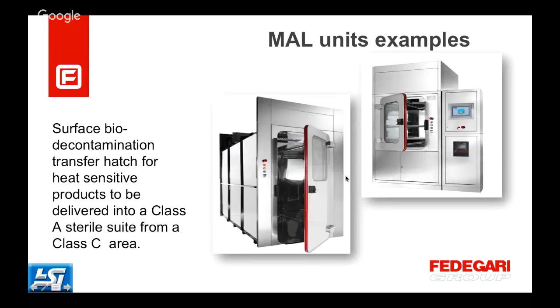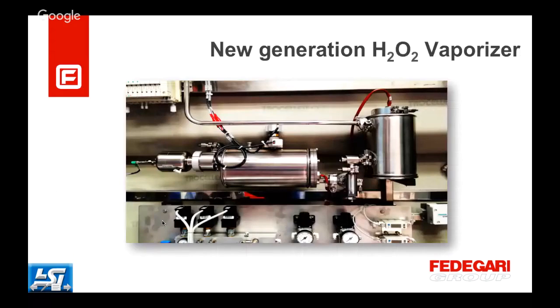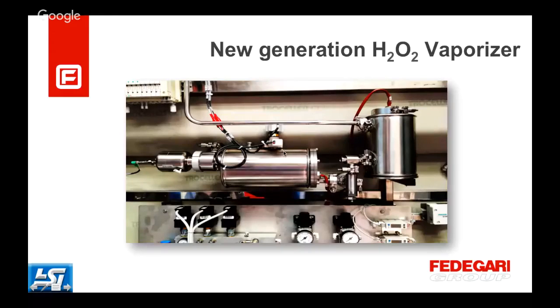So, some pictures of this kind of equipment. You can have a small chamber, or even a floor standing pass-through chamber, so you can introduce even trolleys inside the transfer hatch. Here we have the vaporizer. We have the dosing pump for hydrogen peroxide. This is the buffer tank that holds a fixed amount of hydrogen peroxide in order to be sure that we can finish the cycle that has been launched.